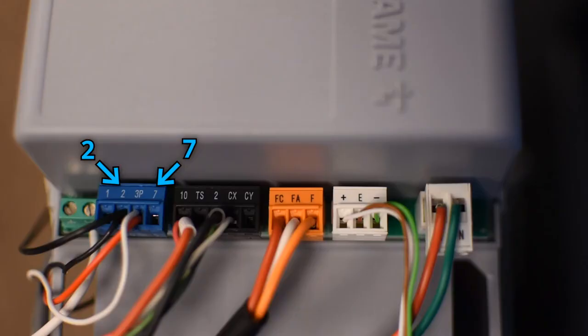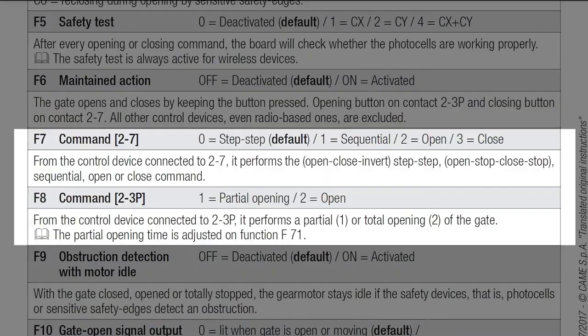To send a command using an external device, like a push button, you can use pins 2 and 7 as a normally open contact and select the function you want in F7. Also, the pin 3P can be used and assigned in F8.